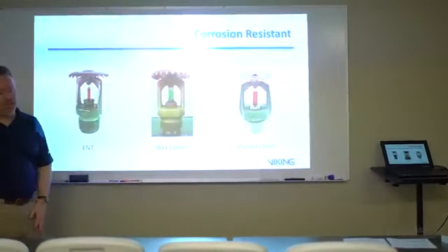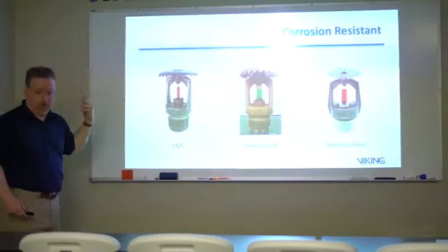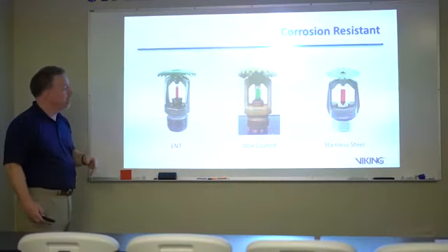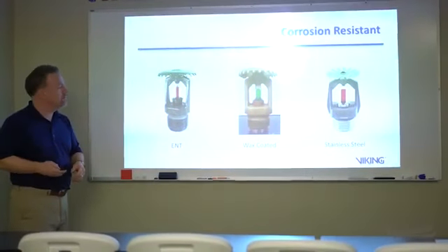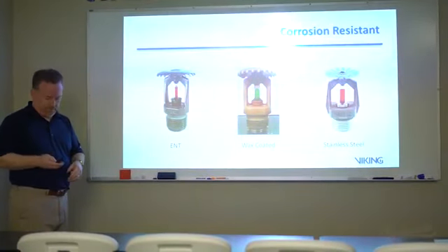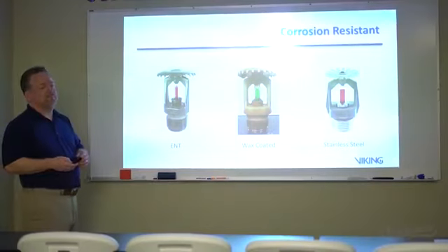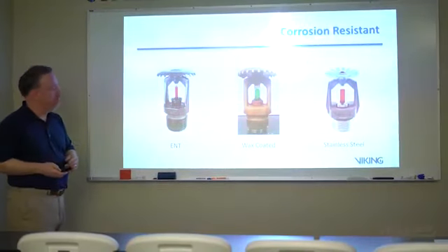And finally, much more expensive is the stainless. Absolutely. But it's possible. Those are your three options in a corrosive environment. One thing, guys, wax coated is standard response only, so we'll never have that in the new construction world down here any longer. The only time we're selling that wax coated head is really replacements, and I'm almost always moving people to the nickel Teflon, the ENT head, at that point as well.